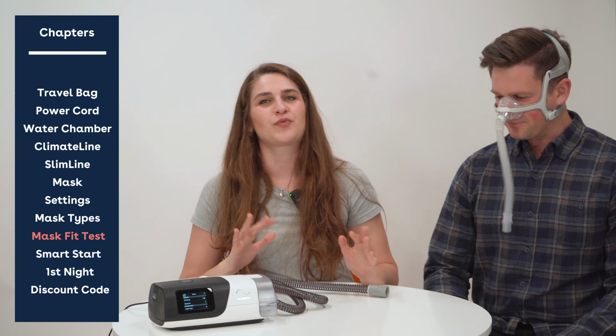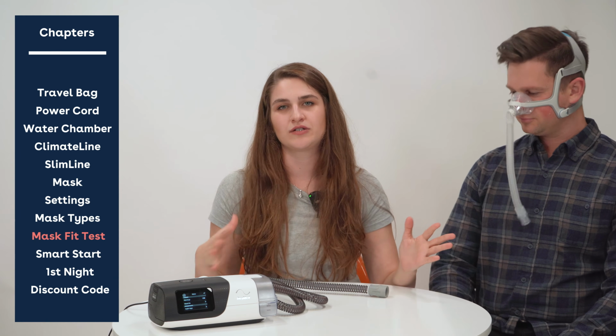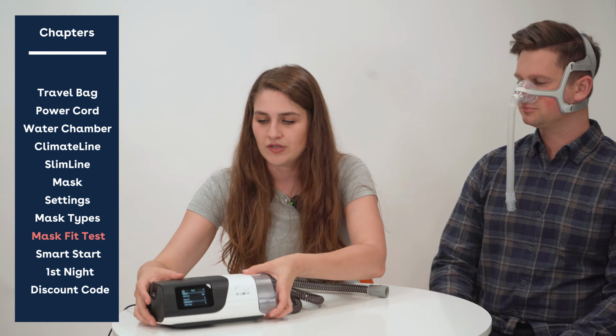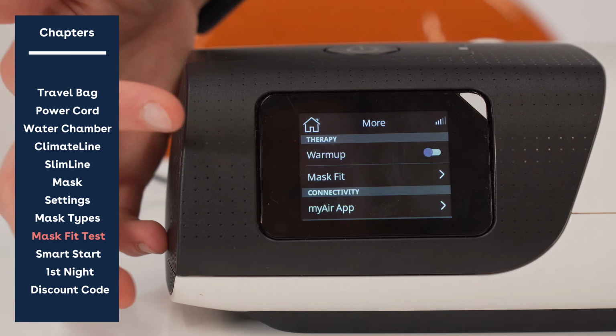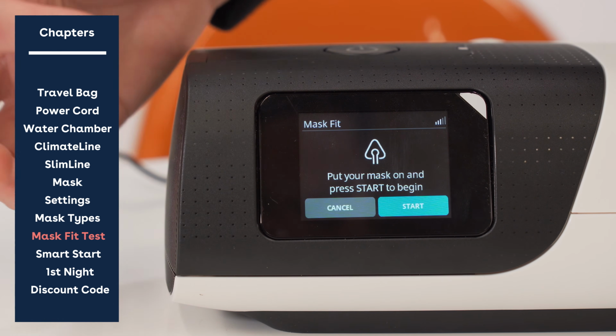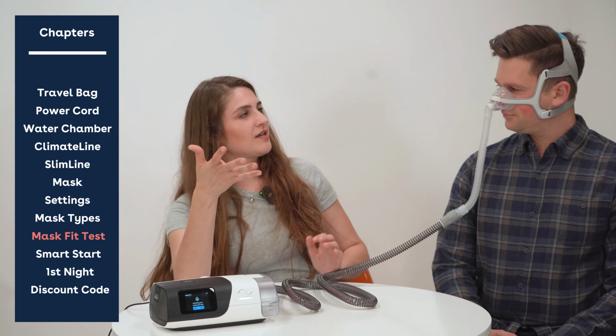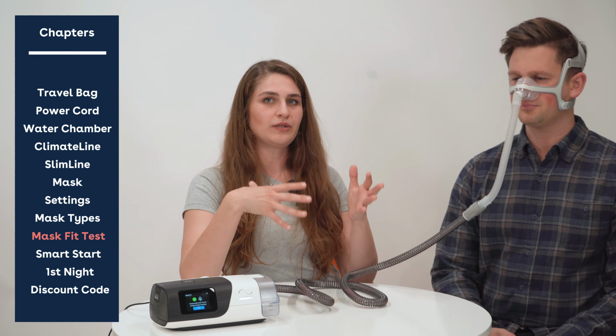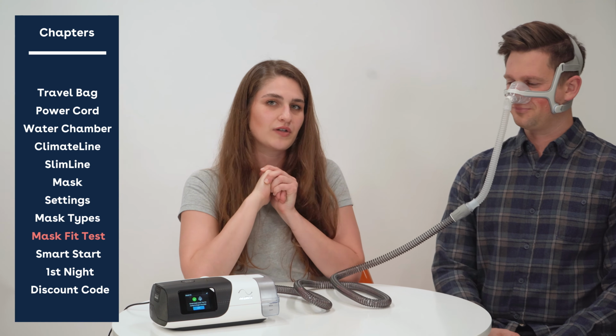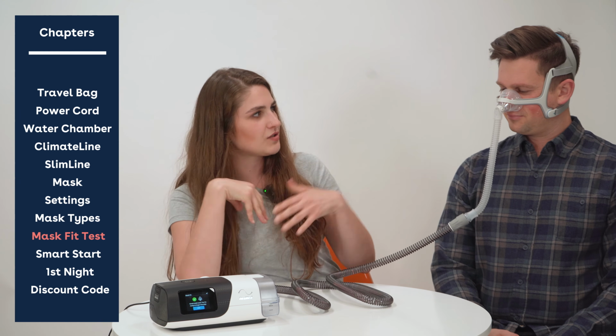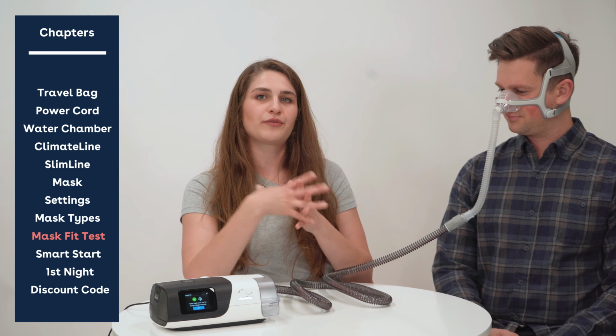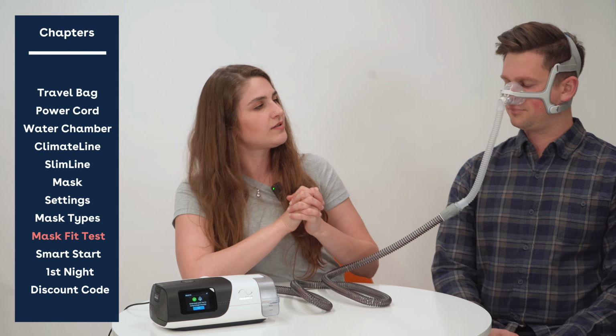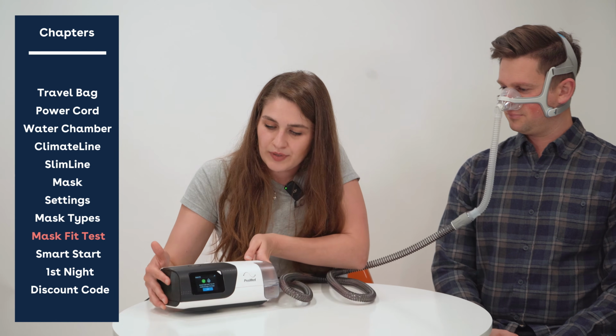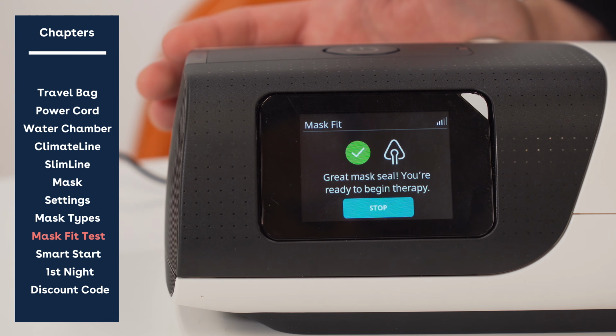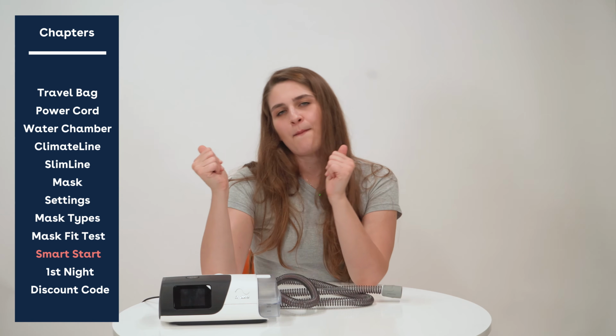So the mask fit test is probably one of the most crucial parts of ensuring that you're adjusting your mask properly without over tightening or over loosening. So this is going to be located in the More menu on your AirSense 11 device under the words mask fit. So this test is going to have the pressures fluctuate a little bit. They're going to ramp up and down to ensure that we have a good seal at low and high pressures. So Max will be breathing in and out through his nose only, as you should on a nasal mask. And the device itself will display if we have a good seal or not. Great mask seal. Machine check, mask check.